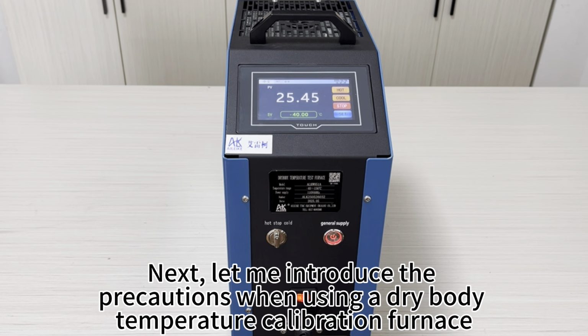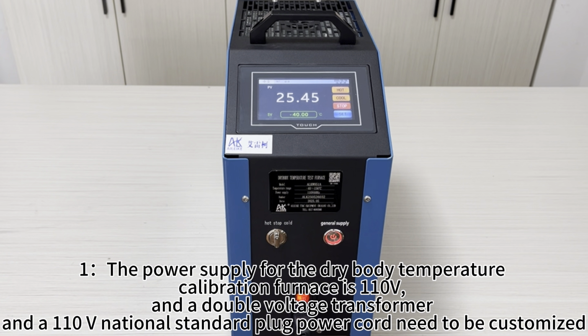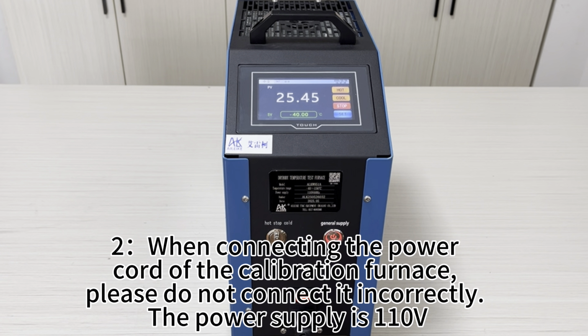Next, let me introduce the precautions when using a dry body temperature calibration furnace. First, the power supply for the dry body temperature calibration furnace is 110 V, and a dual voltage transformer and a 110 V national standard plug power cord need to be customized. Second, when connecting the power cord of the calibration furnace, please do not connect it incorrectly. The power supply is 110 V.